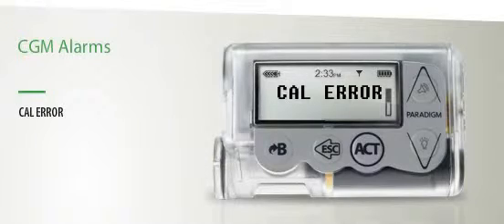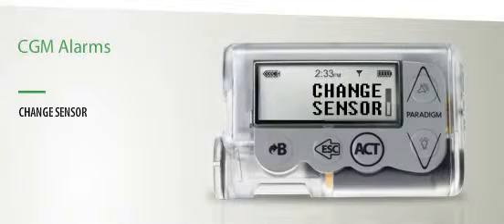Cal error. This indicates that there was a calibration error, probably because the capillary blood glucose from your fingerstick reading and the sensor are incompatible. To resolve this, recheck your blood glucose and enter a new reading. Change sensor. This occurs if 2 consecutive calibrations are unsuccessful, or if you have worn your sensor longer than indicated.